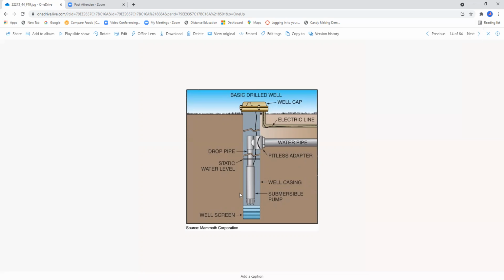Now, the main thing you got to look at if you're going to utilize well water is the mineral content of the water. If the mineral content of the water is high, you are going to have problems with the heat exchangers becoming calcified and insulated due to mineral buildup. So you got to be aware of this. Now, if this water is used for drinking and for a ground loop heat pump system, there has to be a separation, because if there isn't, if you add any chemicals, obviously this will affect your water supply. So there are some careful considerations that need to take place when utilizing a well.